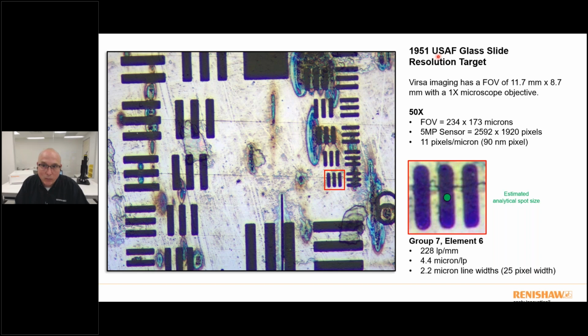So I've had this 1951 US Air Force resolution target in my bag for 20 years. And it really looks like it. It's really dirty. It's got all sorts of laser burns on it. This bar here is group 7.6. This is the smallest feature on the bar. Those line widths are 2 microns wide, and I have approximately 25 pixels across that line width. So my pixel resolution with a 50x objective on the Virsa spectrometer is very, very good. I'm getting really high spatial resolution. I can visualize things very clearly. The white light illumination is perfect, I believe. And then your analytical spot size is going to be roughly about half of that. So you're getting roughly about a 1 micron laser spot on top of there. So you can very easily position these probes on top of very small features and be able to acquire spectra confocally on top of those features as well. So that's one big advantage as well.